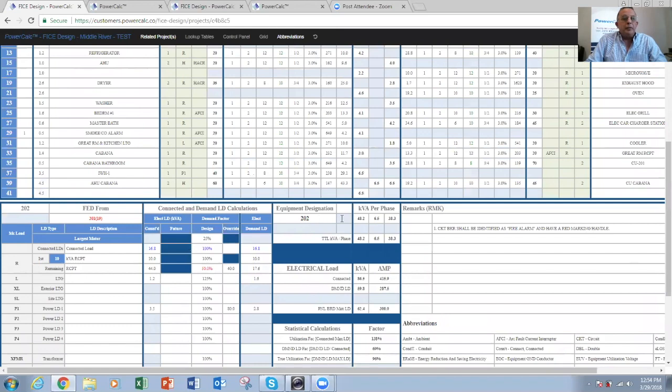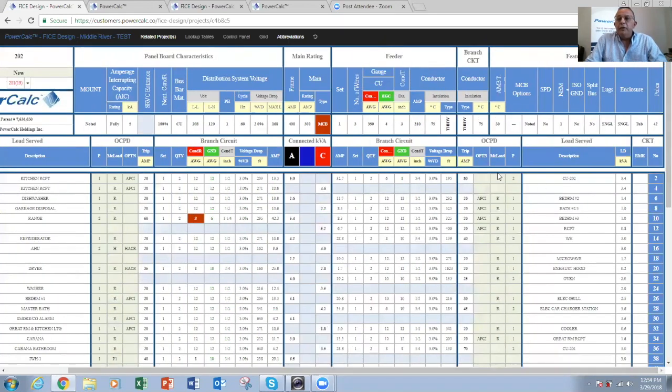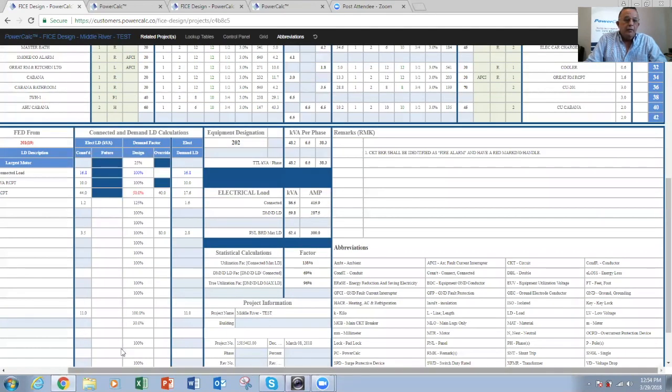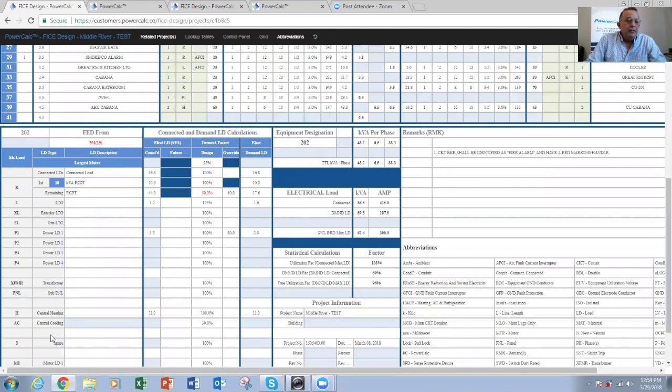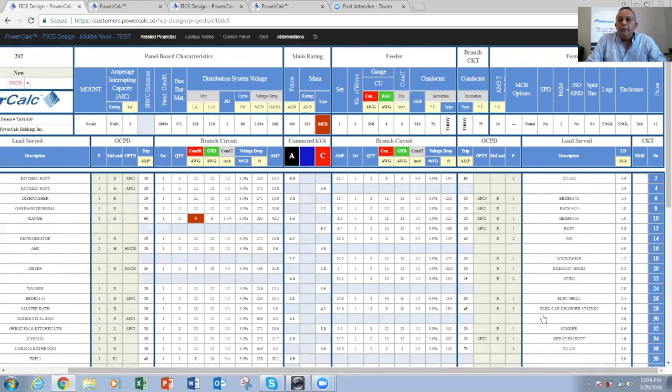So on this particular panel, my design engineer forgot to go ahead and put a load type at the condensing unit. So when I looked at the load tabulation here, there is no AC. See, it only lists the heating of 11 kVA. All right, so let's go back, and I need to go ahead and update my panel. Just select this in here. And also notice that the trip amp is 80.